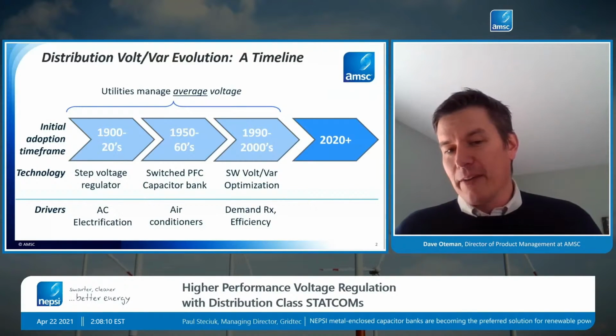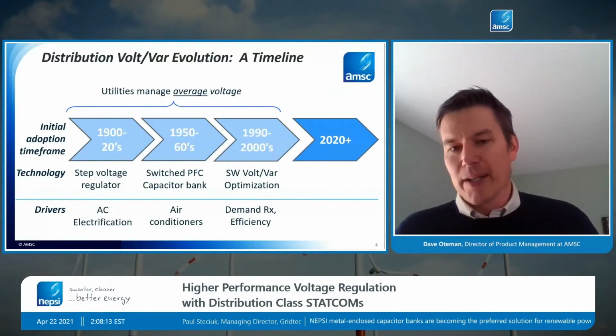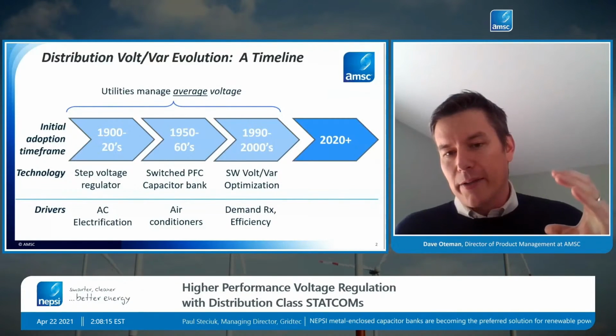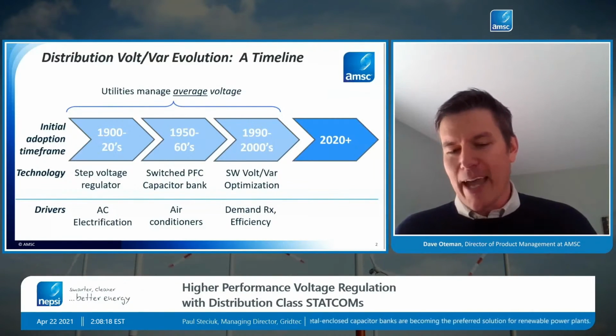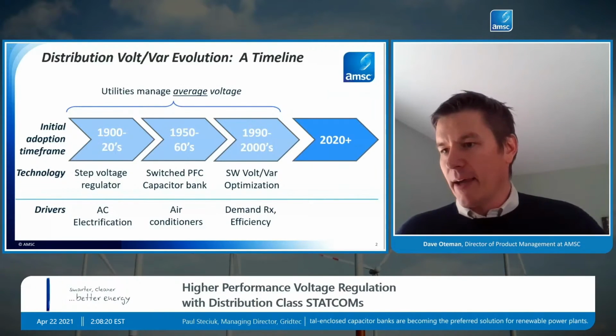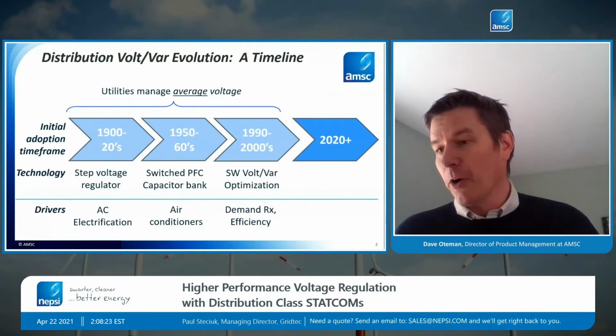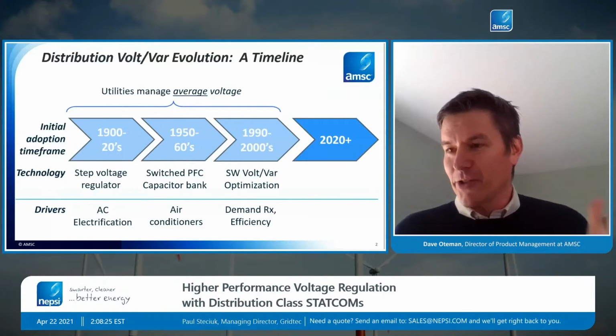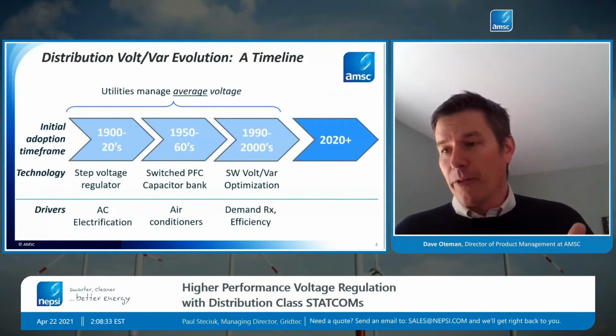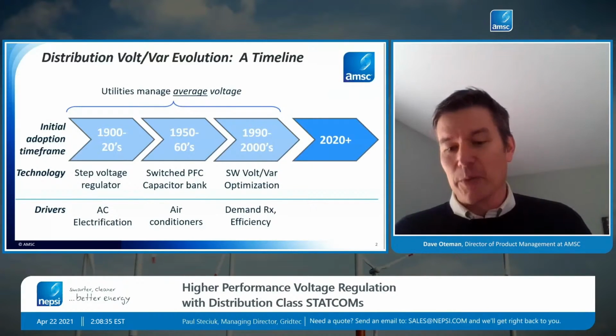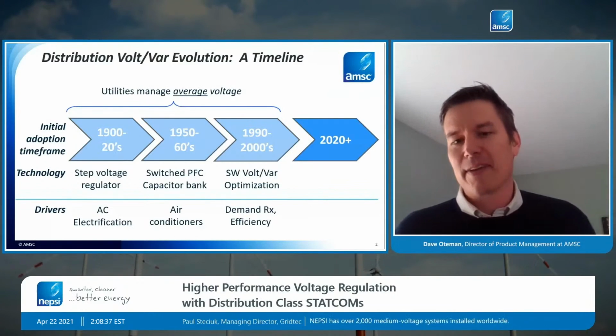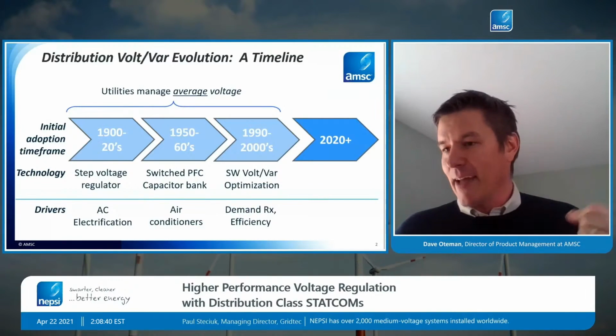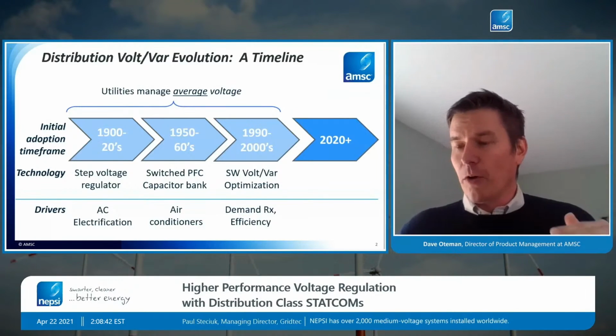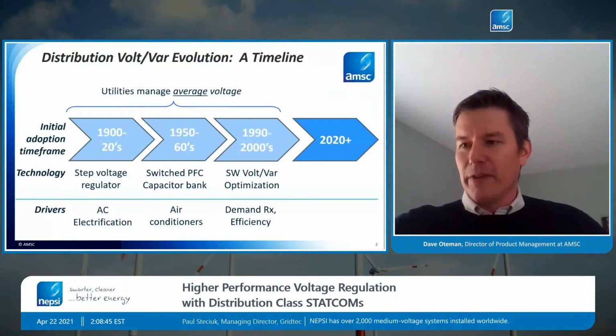From a voltage and power factor correction standpoint, this was the first time utilities really started to take control of these assets from a centralized control standpoint. Previously we had local controllers just turning on and off these devices, or tapping them based on local knowledge. Now with the advent of fast and reliable wireless communications, utilities were able to take it to the next notch of really controlling large arrays or fleets of devices.